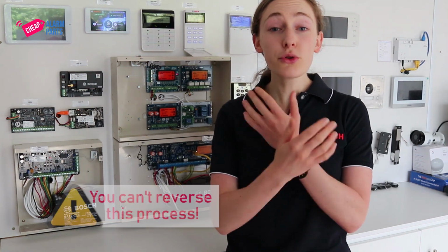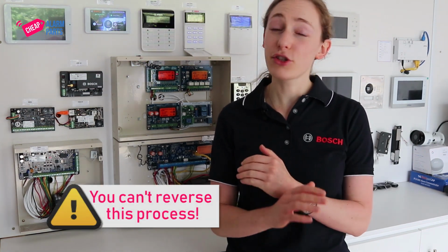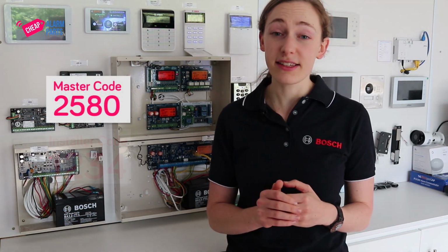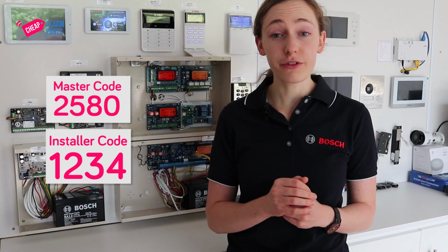I'm going to show you how to default a Bosch Solution 2000 or 3000 alarm panel. Remember that when you default the panel, it will lose all of its programming and there is no way of getting it back. The master code will default to 2580 and the installer code will default to 1234.